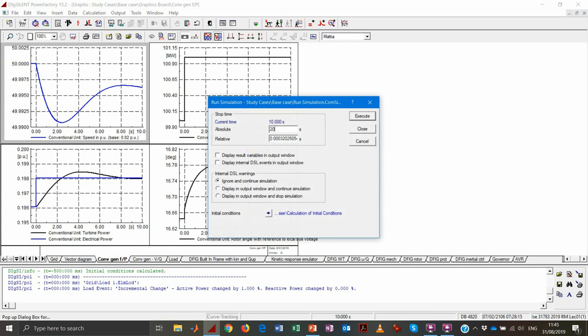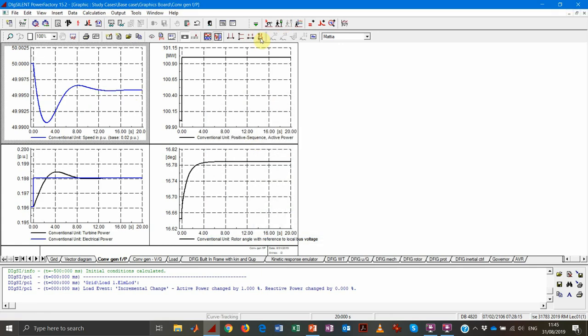To be completely sure this is a new steady state and a feasible operating point, we continue the simulation a bit longer. The steady-state frequency we reach is 49.996 Hz — a bit lower than the nominal 50 Hz, which makes sense because we increased the load slightly. The system is under control because we have our governor — the control system driving the electrical generator — performing the control action and keeping the rotational speed under control.